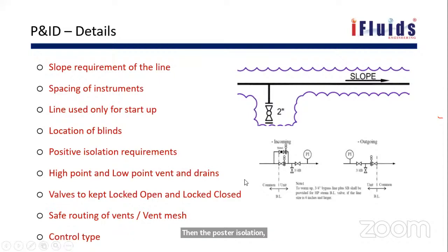Positive isolation in the sense, if you are going for a pump maintenance, like the pump will be going for a maintenance of 1 week. For 1 week we cannot just isolate the valve and do the work, because the valve may pass over a period of time, due to high pressure or any upset in the upstream condition. In that case, if the pump is in open condition, the liquid may pass and come out and create a hazard. So to avoid that, they will provide a plate blind. Plate in the sense, they will completely blind it. So those things will be captured in the drawing.